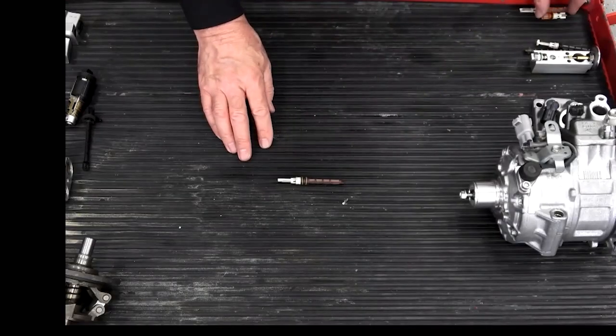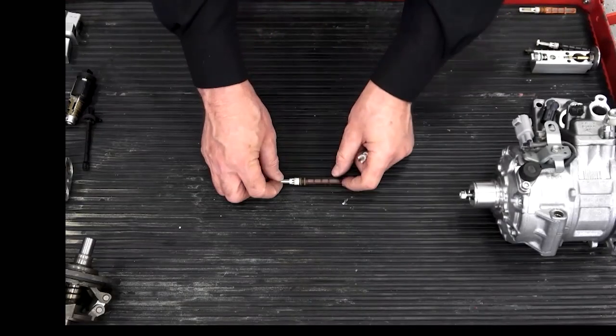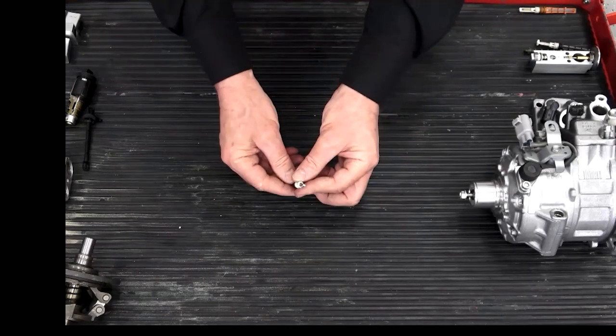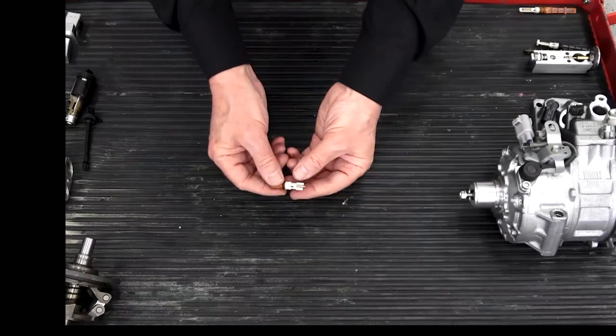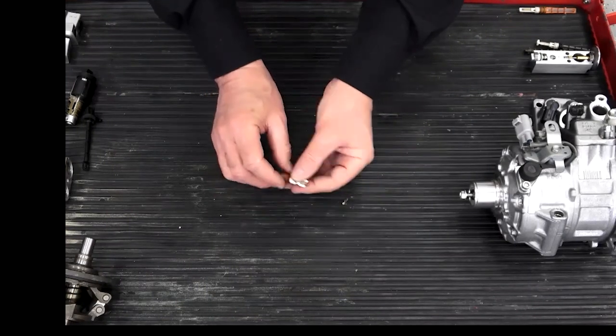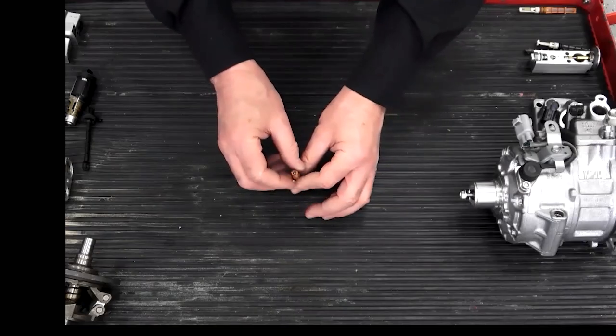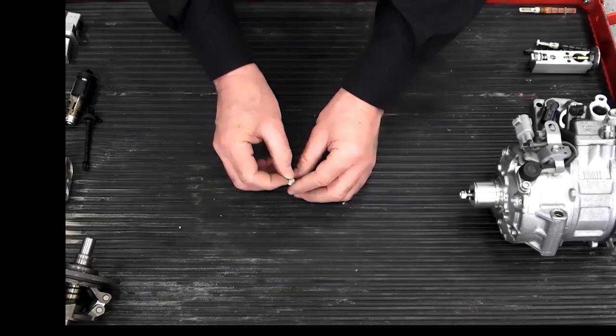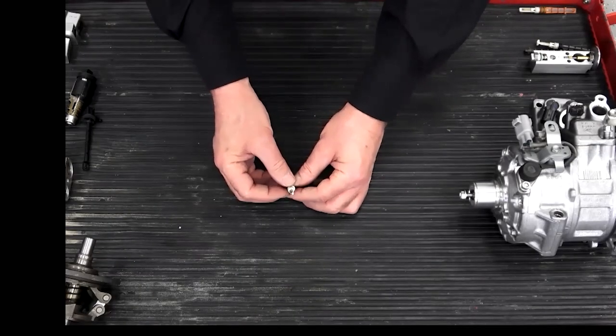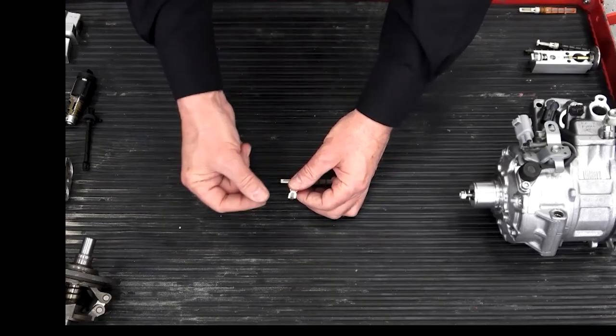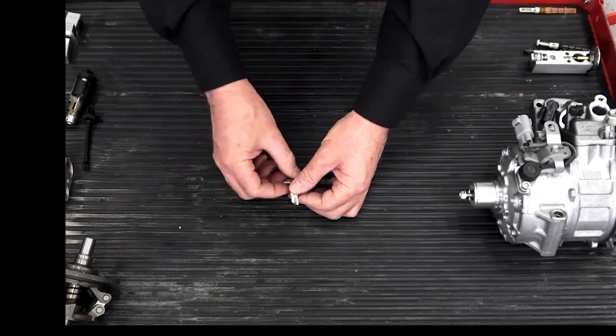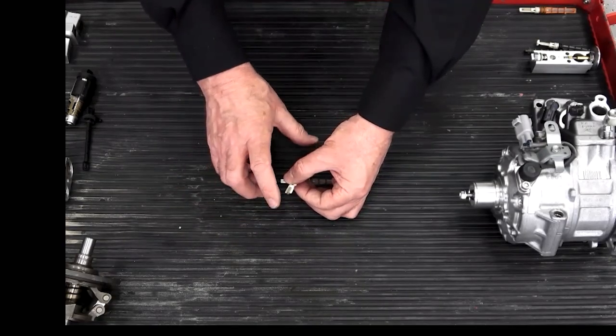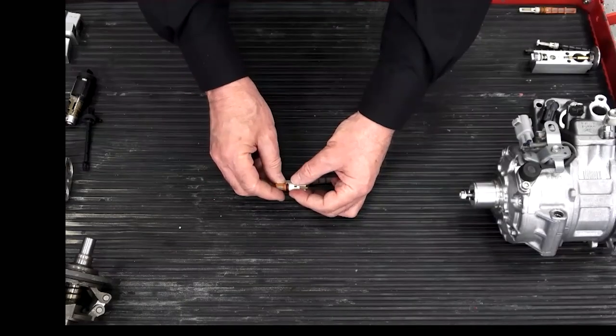I'm sure you've changed plenty of those, but if you've ever cut the end of one of these, I've cut the end off here. In an orifice tube, there are no moving parts, there are no valves. It is simply a tiny tube, just a tiny brass tube. It is simply a restriction to refrigerant flow. That's so I get the pressure differences that I need to make air conditioning work.